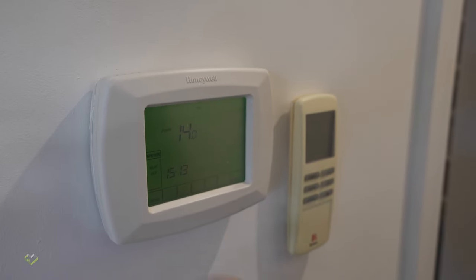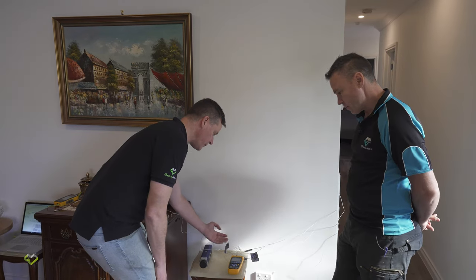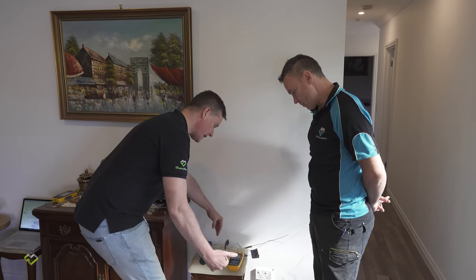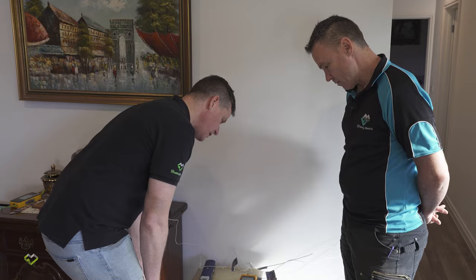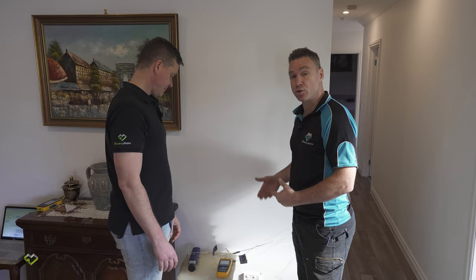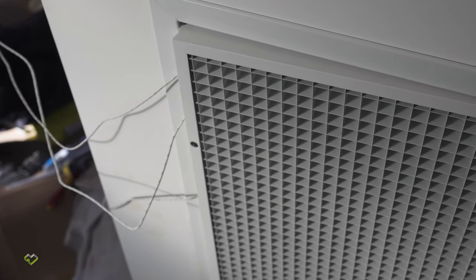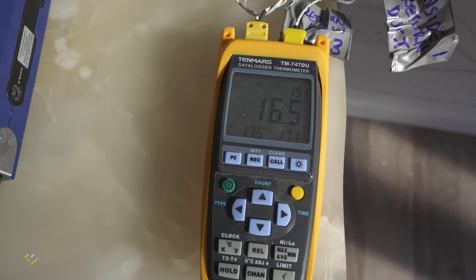We've been running this now and it's quite slow — we still haven't reached 21 degrees. We're getting a warmer temperature at the bottom of the return because clearly a lot of the heat produced by the ducted heating system is making it back to the return, or some of it is at least. The house is just dawdling at around about 16 to 17 degrees. This is clearly not a functioning return. The temperature up in the roof is basically the same temperature as the air going into the ducted heating return — 17 degrees and 16.5 degrees, very similar.